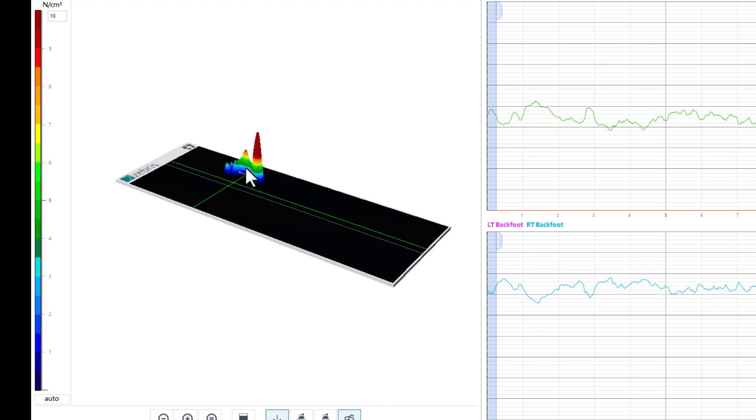Optionally, the pressure scale can be adjusted individually in each measurement. Changing the pressure scale causes a proportional change of the display's pressure height in the 3D image. It does not change the measurement data, only the depiction. To see this well, in the following we always look at this footprint.